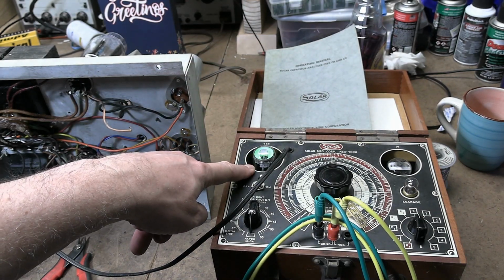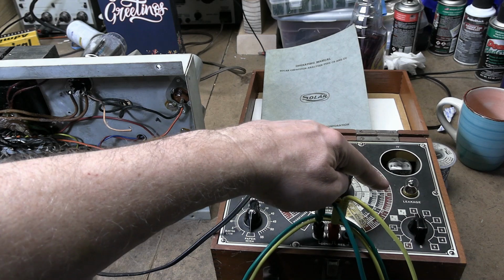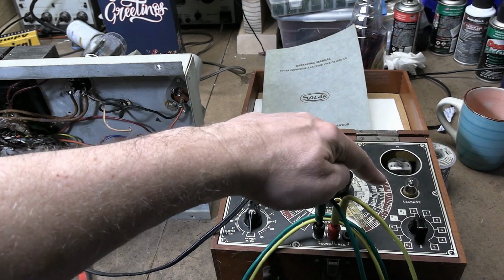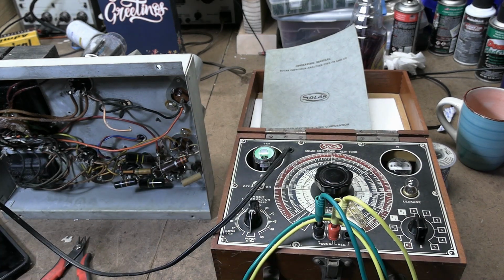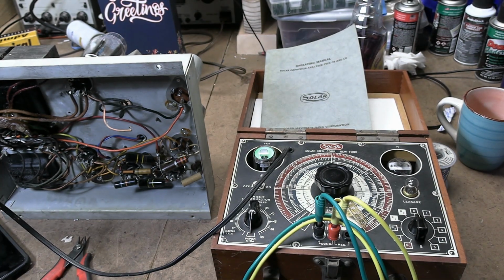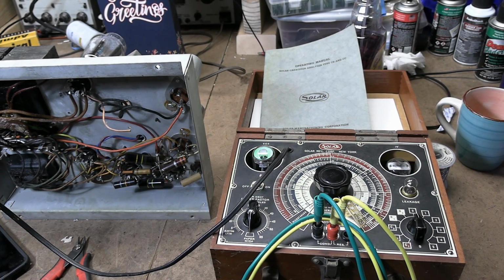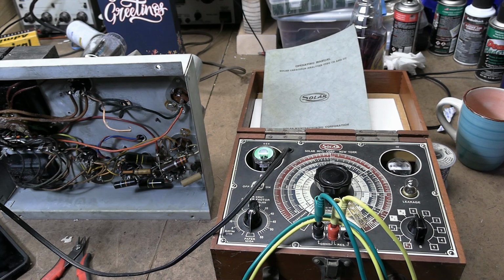It has a neon bulb that flashes to indicate how much leakage there is. If it never flashes, you have very low or no leakage. If it's flashing very quickly or staying on, you have a lot of leakage. There are fancier testers that will show you the actual leakage current in milliamps, or of course you can put a meter in series with this setup.